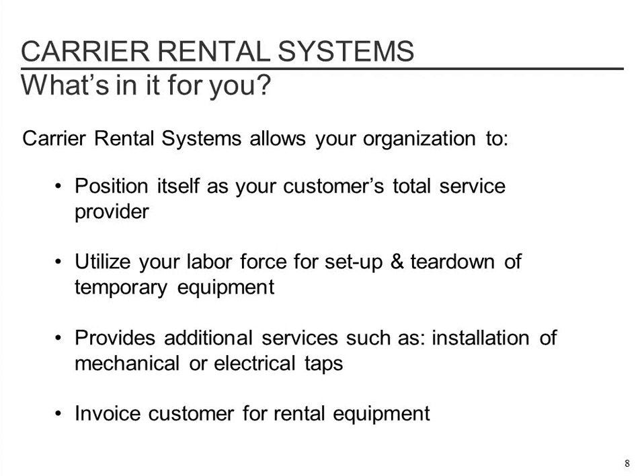It allows you guys to install additional capital installations, such as taps for the fluid connections or the electrical connections. Ultimately, a lot of times, if we're doing a contingency plan, the customer will allocate some funds and they'll pull their mechanical taps to their fluid system to the outside and valve it off so that, God forbid, the day the event the contingency plan is to prevent takes place, they're able to pull up a truck and connect in a chiller just as quickly as humanly possible.